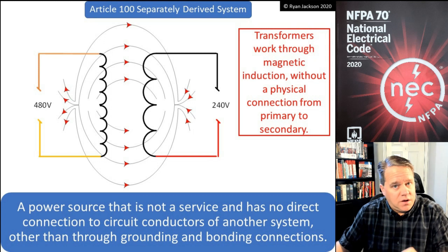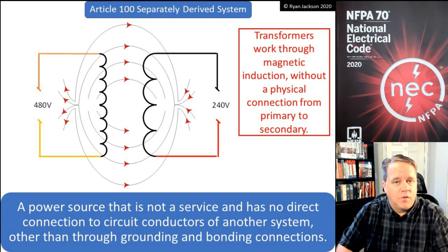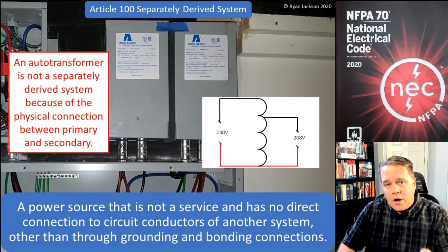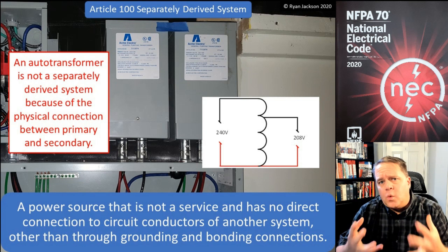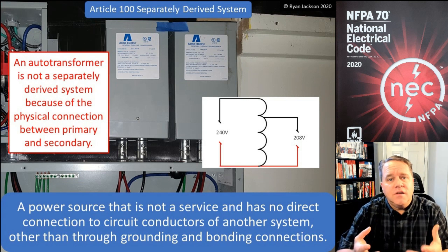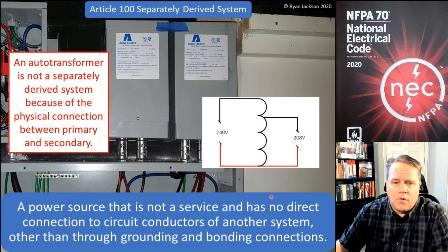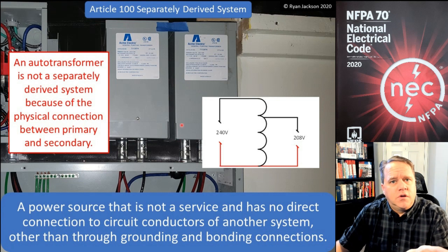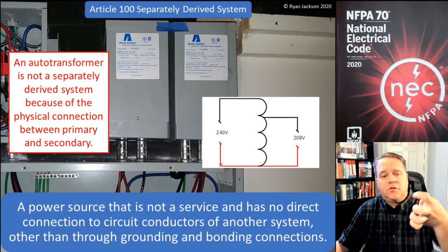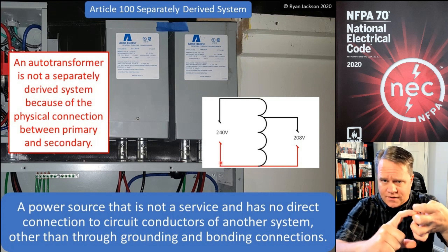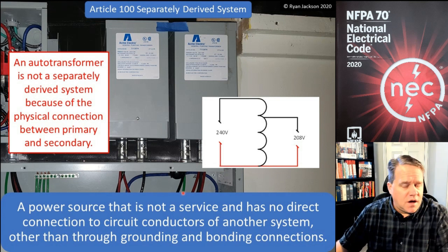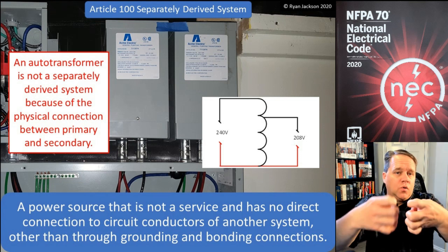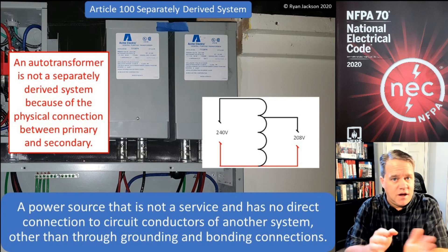A transformer is a separately derived system; however, an auto-transformer — or what we call in the field a buck-and-boost transformer — is NOT a separately derived system. With an auto-transformer, there actually is a direct connection between the primary and secondary. As shown in the diagram, you've got the 240V coil wire and you tap into a portion of it to get 208V out. Because there's a direct connection, it's not a separately derived system. A normal transformer has two separate coils connected only through magnetism.